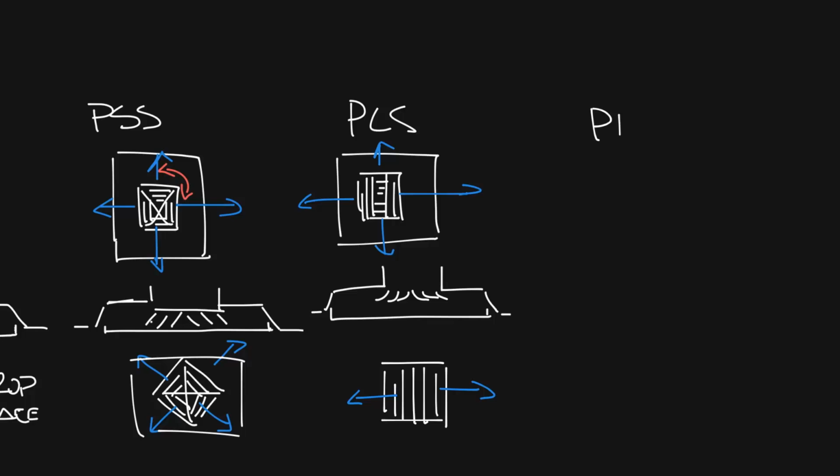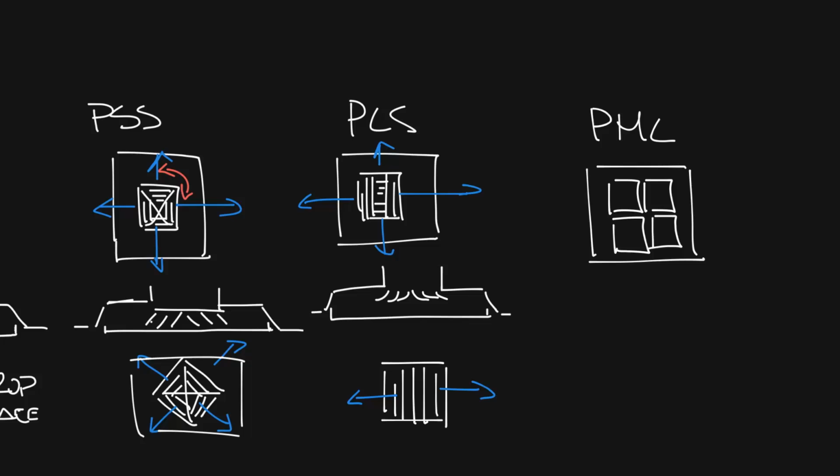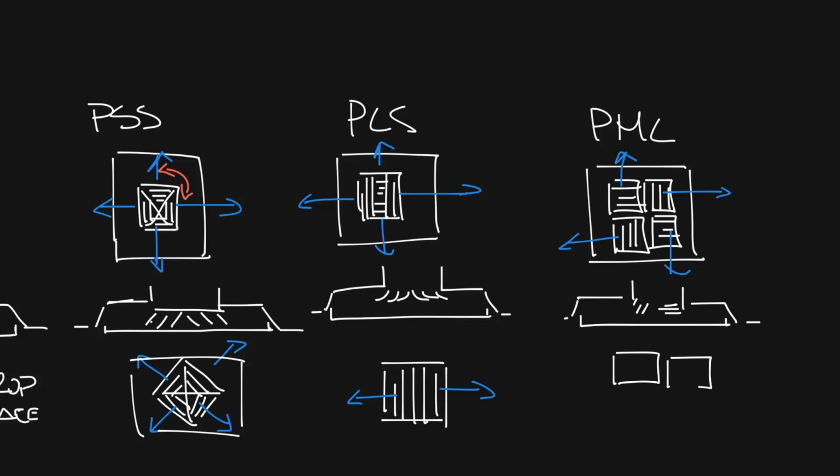Next we have the PML. It has 4 deflectors. It looks sort of similar in my drawing to the PAS, but the deflectors are in the neck of the diffuser, not on the face. So the default setup is a 4-way pattern, but you can rotate these 4 deflectors and get different patterns as well. Like this would be set up for a 2-way pattern.